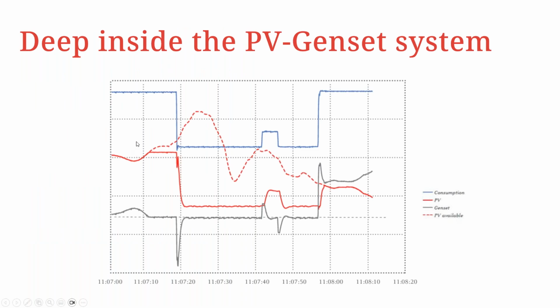Going forward, it is important to note that the reaction time of every PV genset system is of utmost importance, because in a case where the system is not able to react as fast as possible, there could be trouble, especially on the genset side. So we have this real case scenario, a graph of the reaction time of our plant controller. You have the load consumption, and then you have the genset output, which is at this point at the minimum genset loading.